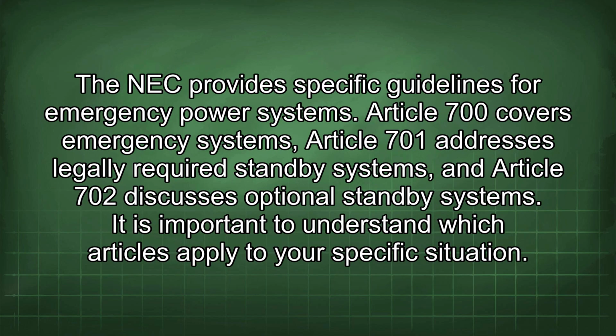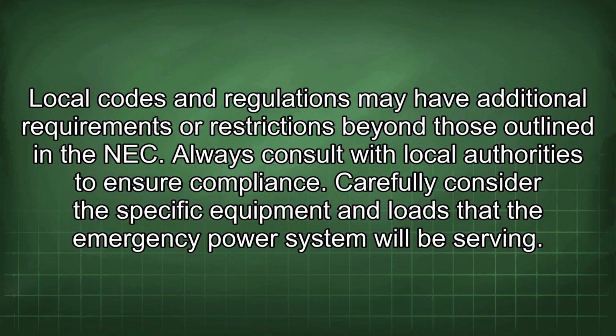The NEC provides specific guidelines for emergency power systems. Article 700 covers emergency systems, Article 701 addresses legally required standby systems, and Article 702 discusses optional standby systems. It is important to understand which articles apply to your specific situation. Local codes and regulations may have additional requirements or restrictions beyond those outlined in the NEC. Always consult with local authorities to ensure compliance.